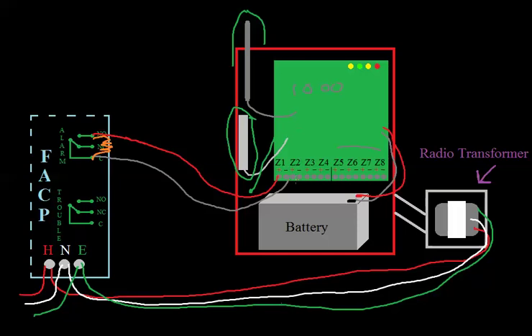Now we'll do trouble. And maybe let's say these are the only zones we're using. Maybe we're only using one and two. And there's a few different ways I can bypass this. I can resistor out the rest of the circuits. But there's a handheld programmer for all these radios. You plug it in and then you could tell it which zones you're using. You could bypass zones three, four, five, six, seven, eight. Well, not nine, because there's only eight zones. But you could bypass all those.